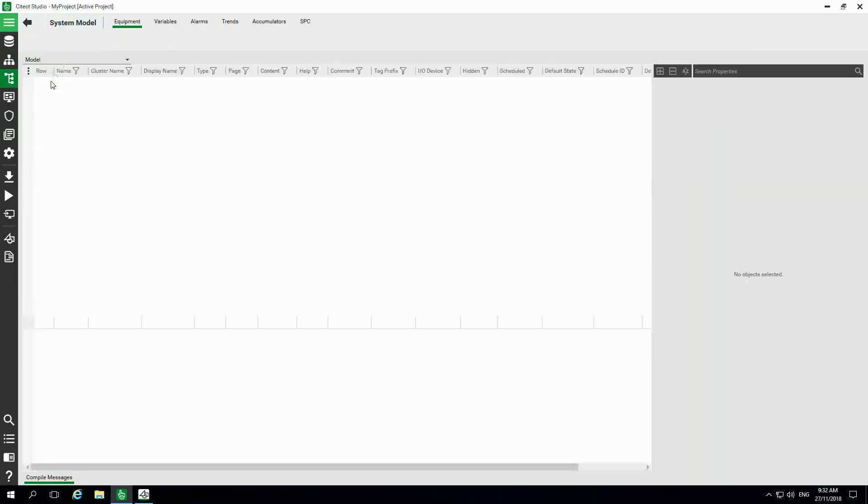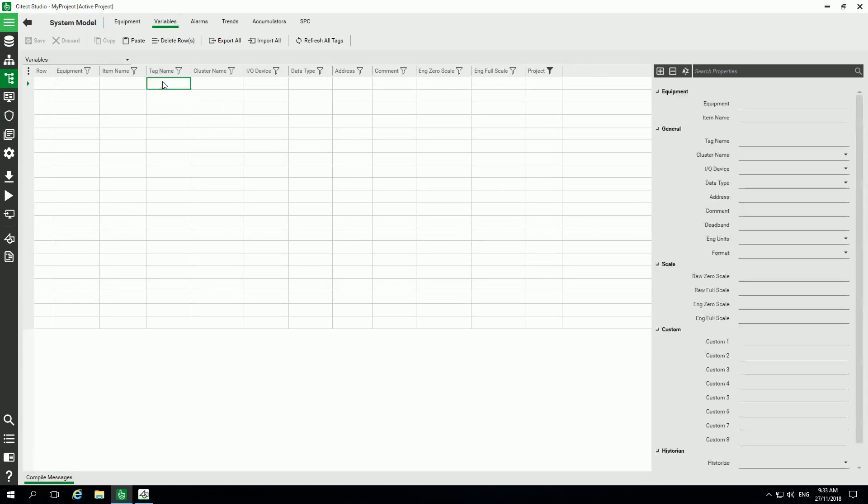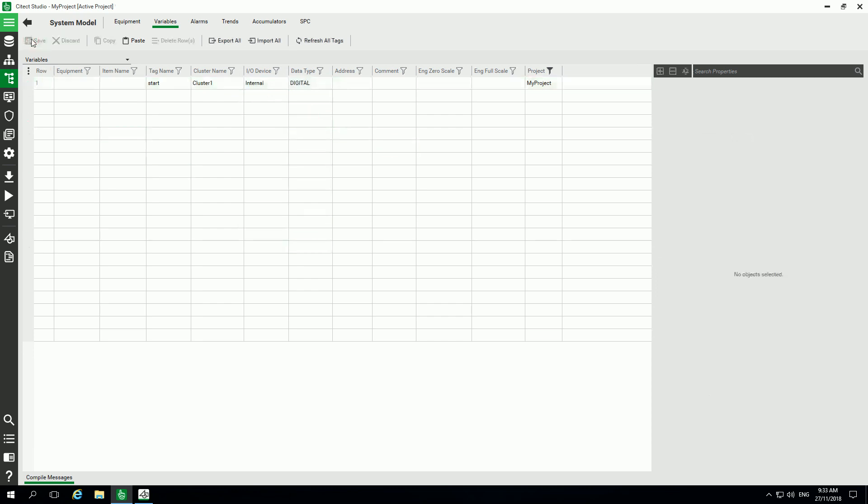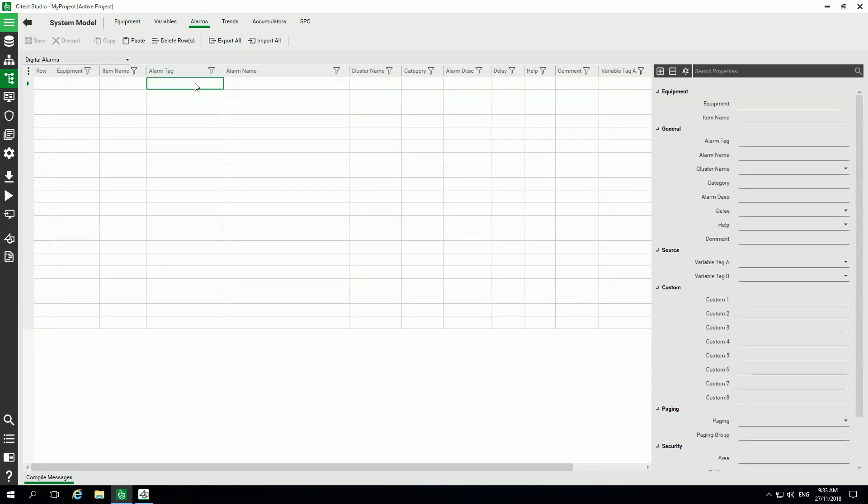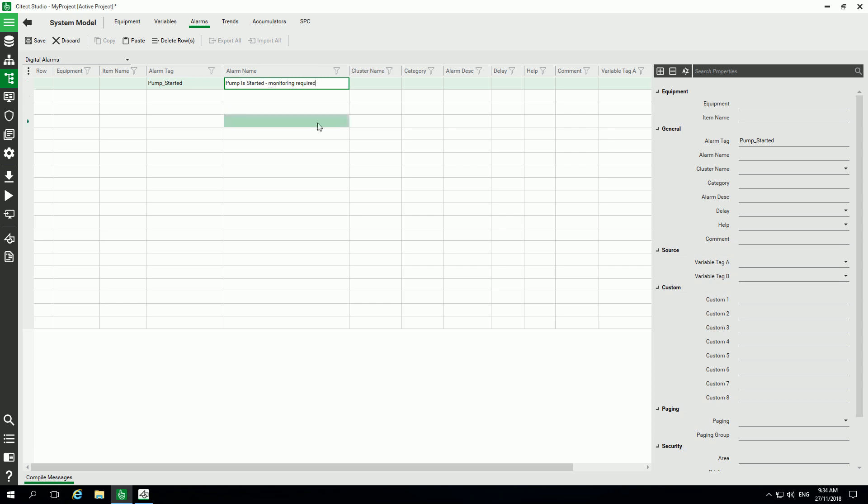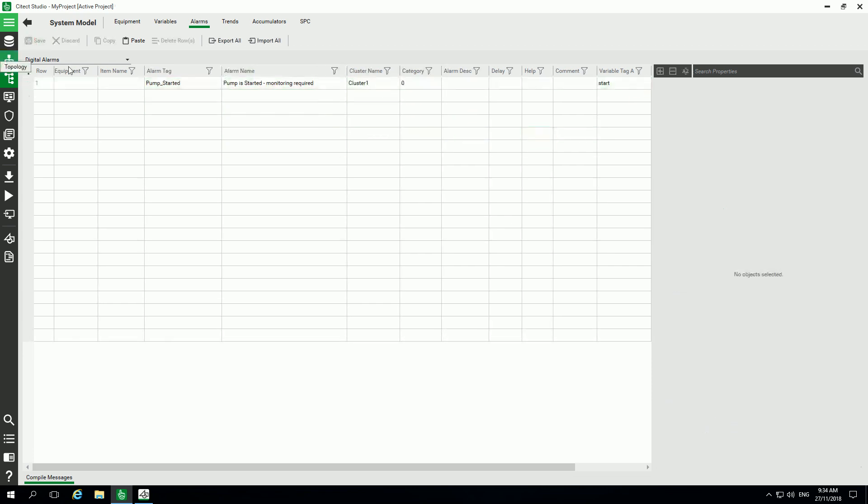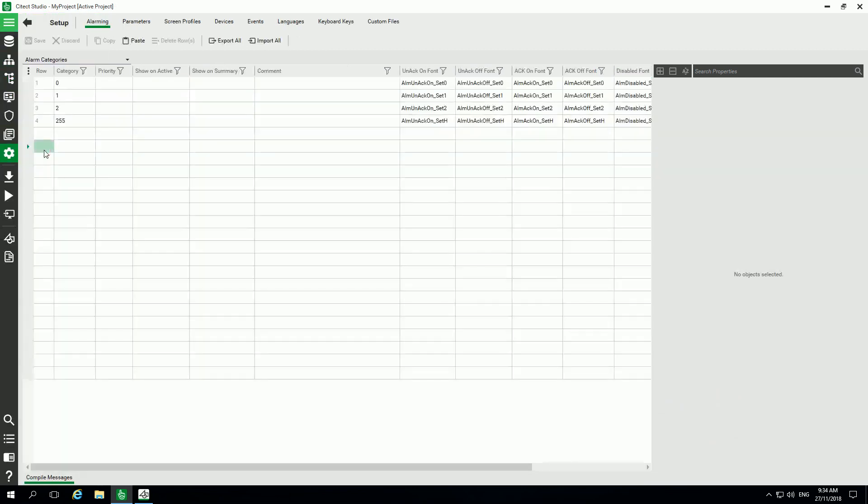In the system model, I will add one variable. We'll call it start variable. Cluster one will be using the IO device internal. It will be digital, and I'm creating as well an alarm for this digital. You give an alarm tag and alarm name, same cluster and category zero, and I'm using the variable start. We see here on setup this already predefined category, so I select the zero one which is the default category for alarms.